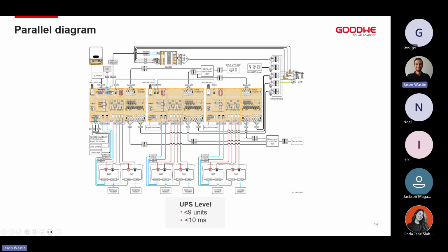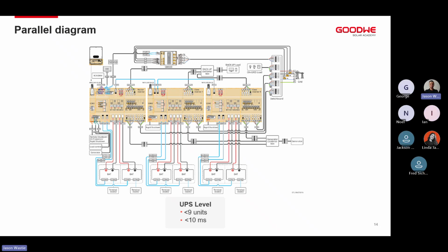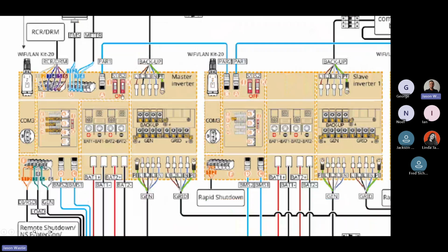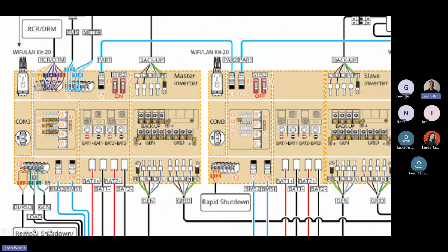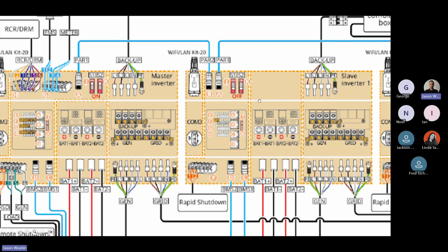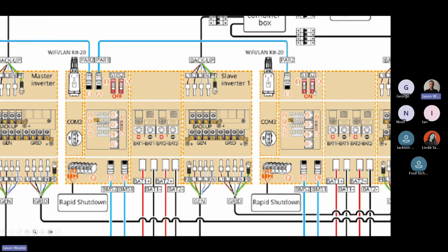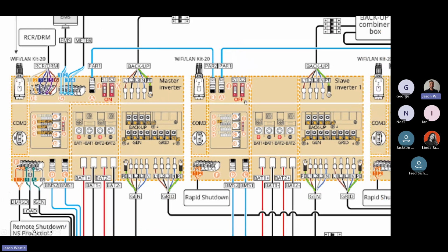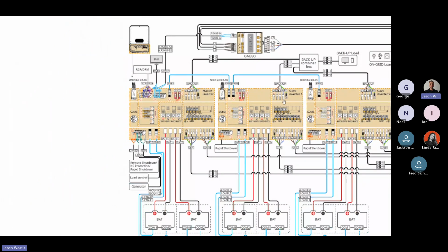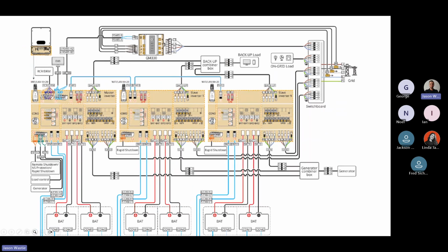The 3 CTs that need to be installed with it are any 5 amp secondary ratio CTs, so a 100 amp by 5 amp CT, a 300 amp by 5 amp CT. So long as it obviously is a 5 amp secondary ratio CT, it will connect perfectly fine. You'll see small things that you do need to just take note of when running parallel on systems. Most importantly is the dip switches. So if you look, there is the master inverter, the slave inverter. First slave inverter will have the dip switches off, and then the last inverter in the chain all on again. All of this is readily available in the user manual, and we can get all of this from there as well.